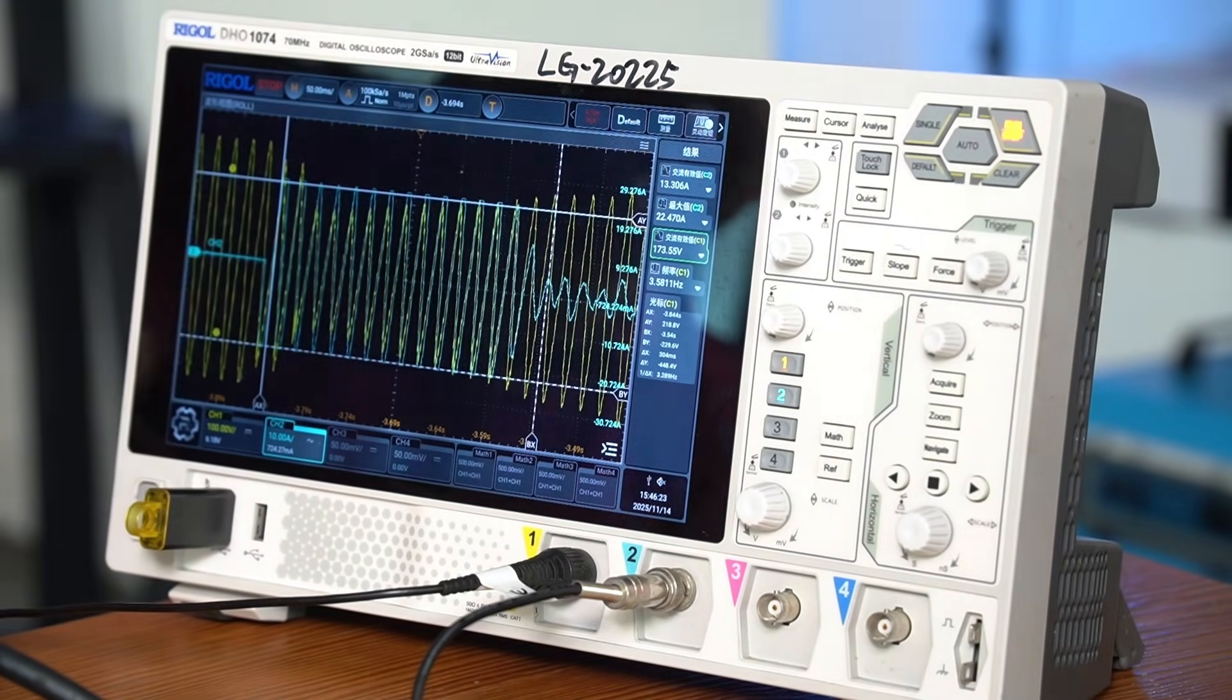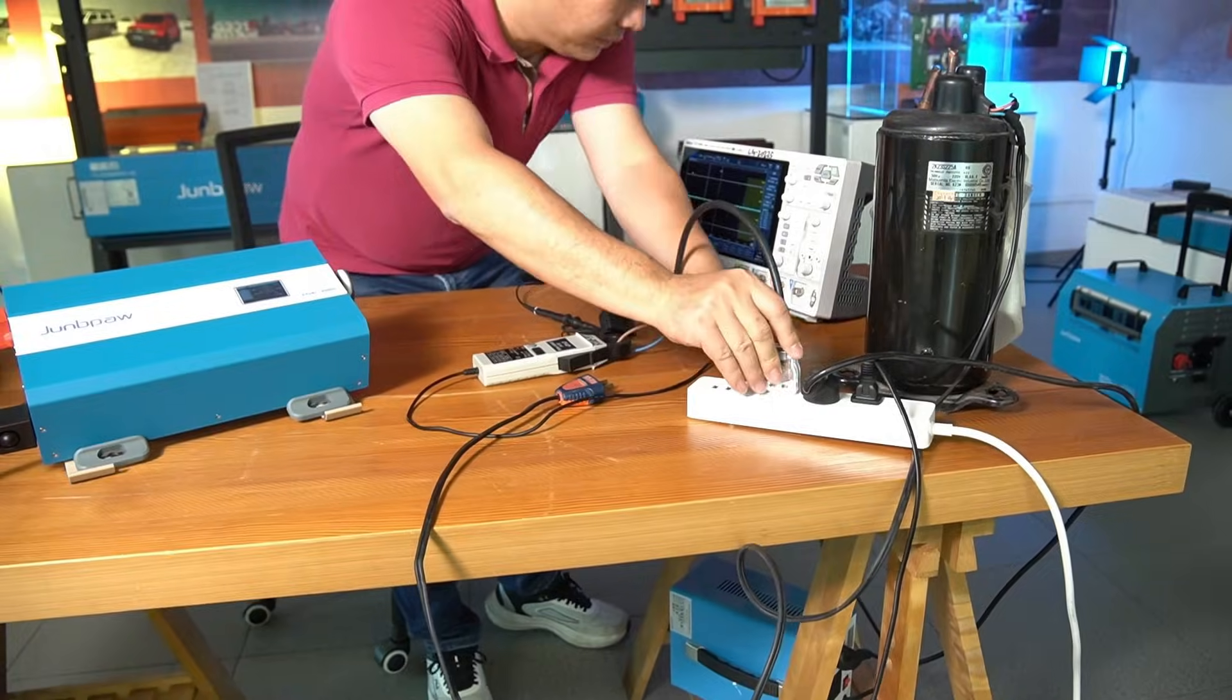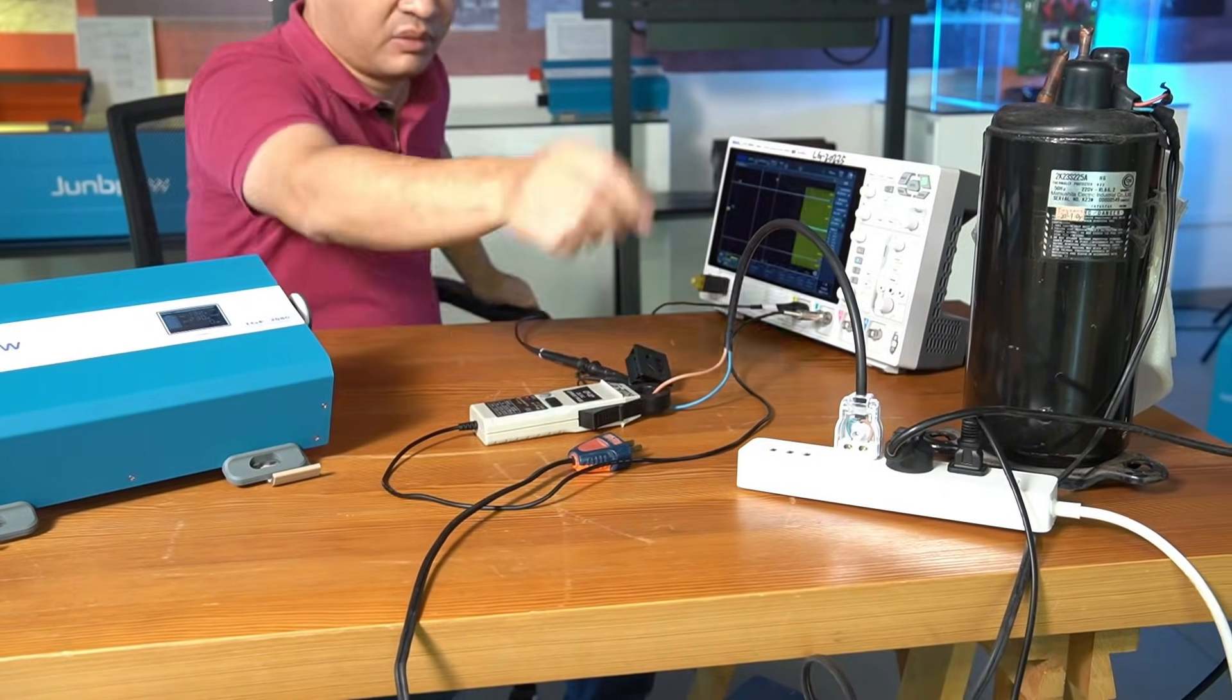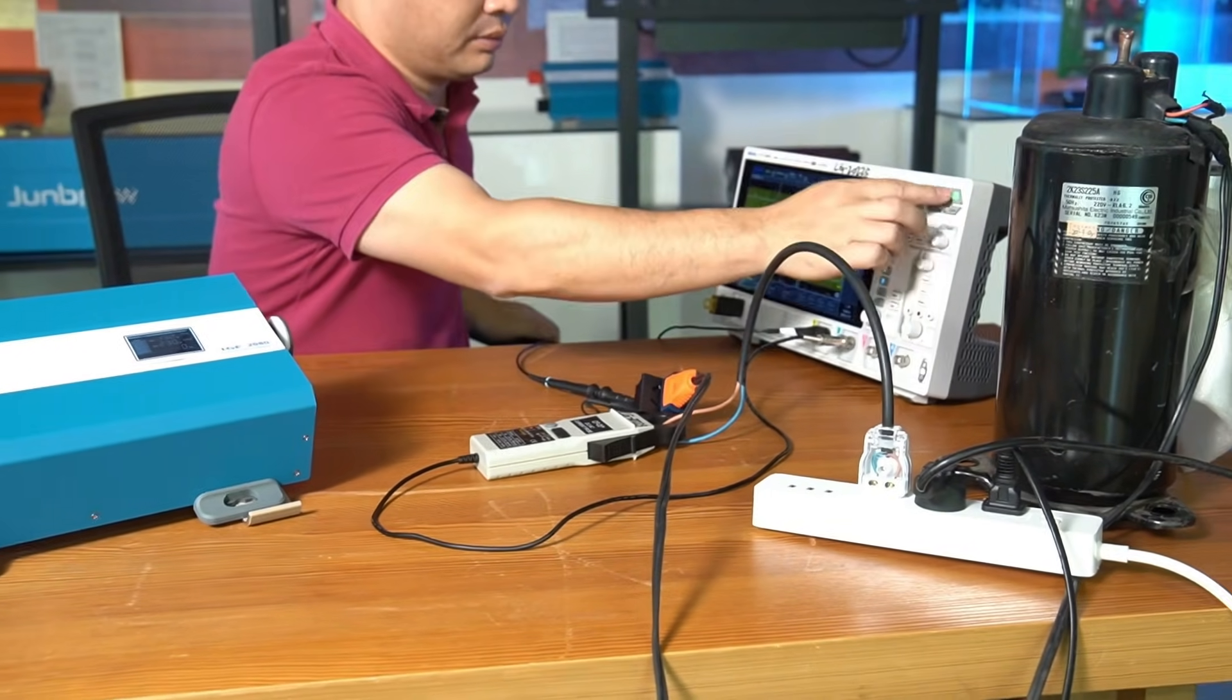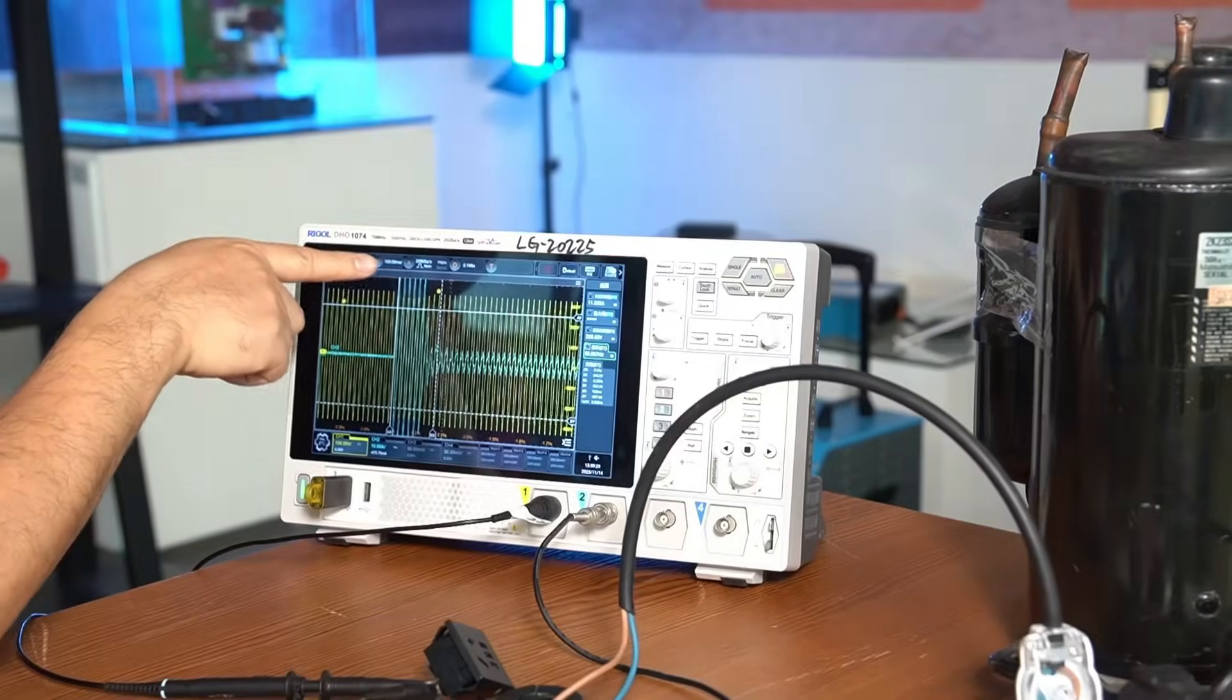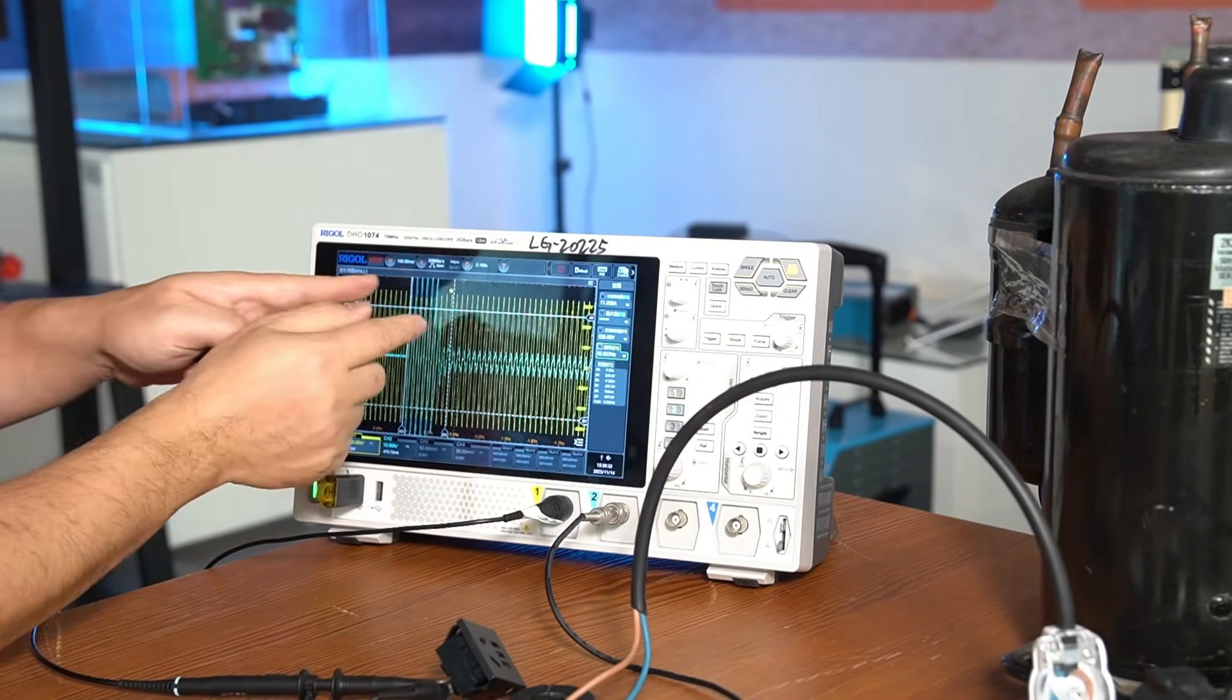For comparison, let's connect the compressor to the mains power and observe the startup waveform. Although the waveform shape is similar, the startup time with mains power is shorter, about 150 milliseconds, whereas it takes 250 milliseconds with inverter.